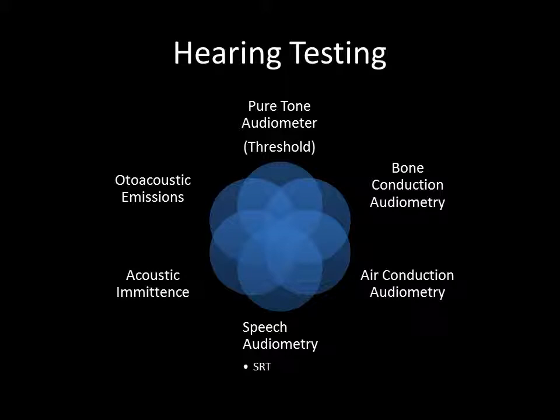A probe is placed in the patient's ear and contains both a speaker for producing a rapid series of audible clicks and a microphone to capture the signal produced by the cochlea. Researchers discovered that in addition to spontaneous sounds produced by the cochlea, sounds could be evoked from the cochlea following acoustic stimulation.